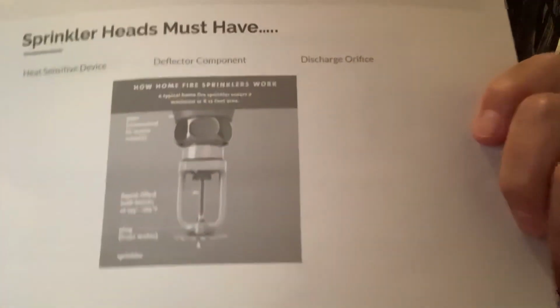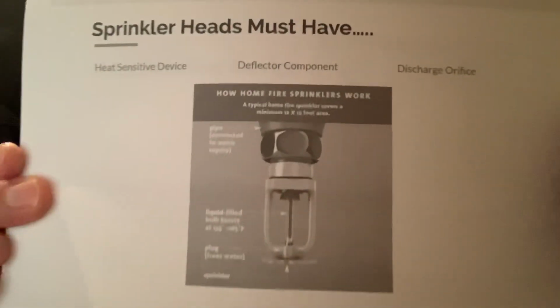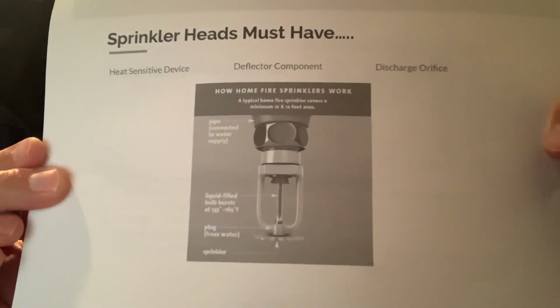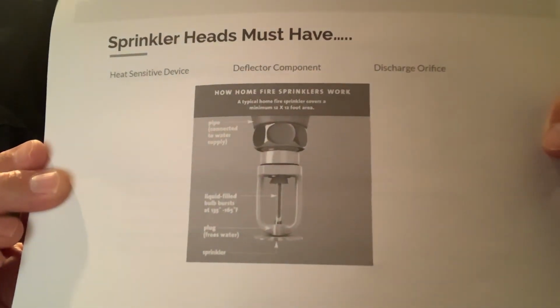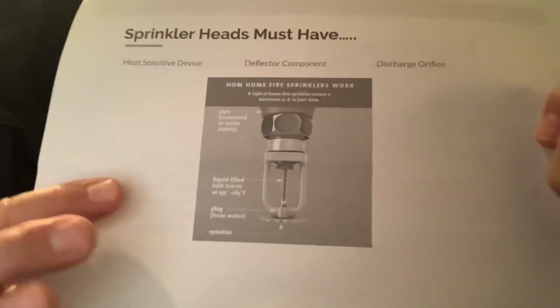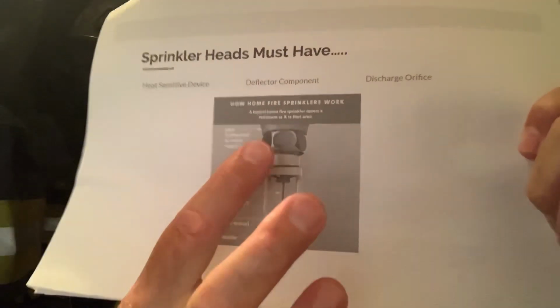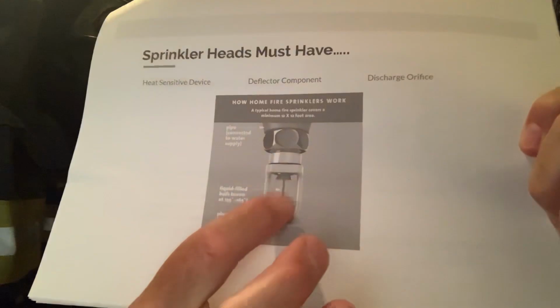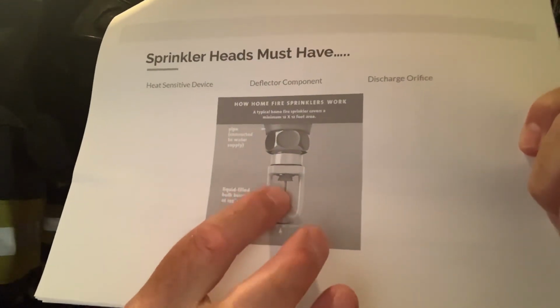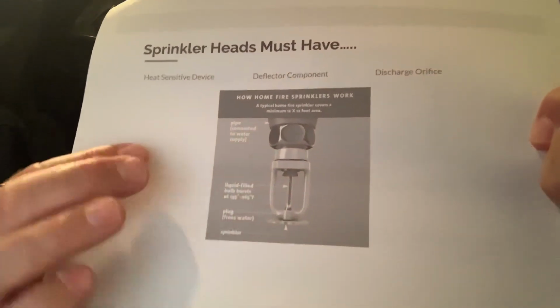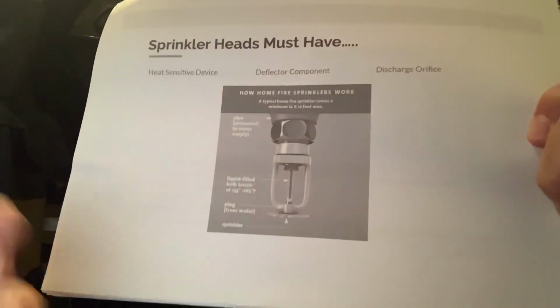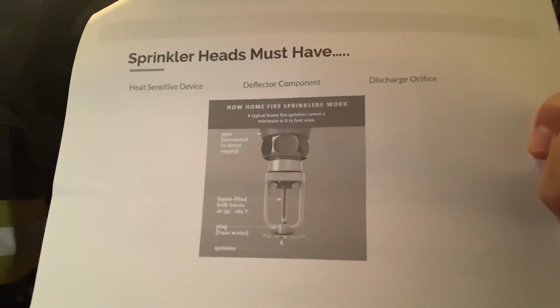And sprinkler heads must have a heat-sensitive device, deflector component, and discharge orifice. There's basically a schematic for your sprinkler head. Okay, and again, the PowerPoint shows you all the breakdown of the sprinkler head, what it has, a deflector component right down here. Okay, it's shut off until something activates, whether it be a frangible bulb. Okay, it has a heat-sensitive device, it will pop and activate. That's your sprinkler head.